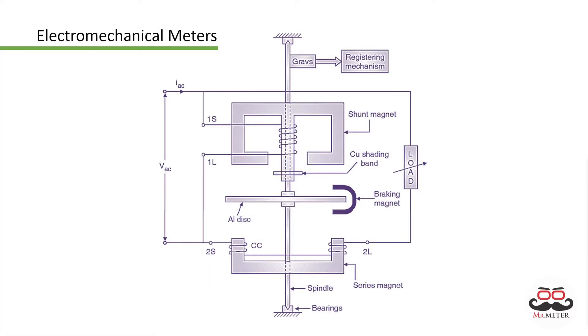The basic mechanism of an electromechanical meter works through induction: a wheel is rotated and this rotation on an axis turns the meter numerator or dials, counting the customer's consumption. In detail, the mechanical meter has two conductor coils that create magnetic fields — one coil is impacted by the voltage going across the conductor, and the other is affected by the current. The magnetic fields generated by the interaction of these coils turn a thin aluminium disk at a speed proportional to the amount of electricity consumed.